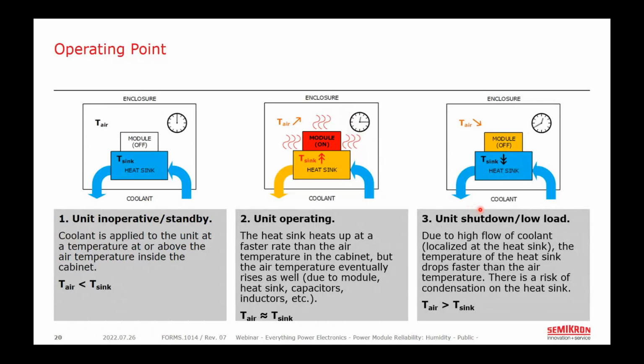In the case of a solar inverter, that might be when clouds move over a group of photovoltaic cells. Or in another converter, there might be a fault and the system is running at full power and immediately shuts off, and the coolant system is continuing to run at its full rate, either full liquid flow rate or full airflow. Both the power module and the surrounding air inside the cabinet are still at that elevated temperature, but the heatsink, particularly for high efficiency liquid cooled systems, is going to cool down quite quickly, possibly reducing the heatsink temperature below the dew point for this microenvironment within the enclosure, and that's when you have a risk of condensation.